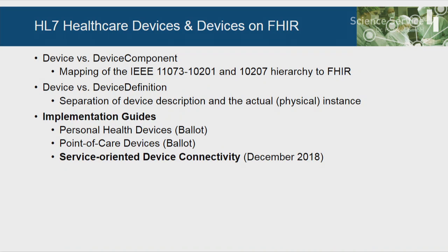Now, we're not the only ones developing standards. For example, HL7 is also very active at the moment, and they've come up with what they call Fast Healthcare Interoperability Resources, commonly known as FHIR. And the good thing about FHIR and SDC is that they have been developed in parallel over the years, and many members of the one working group have also been members of the other, and we communicated a lot, and that means what we reached is a pretty good mappability of those standards. That means we can transfer SDC device data into FHIR resources without a lot of data being lost, in contrast to older HL7 protocols where you'd actually lose a lot of things.